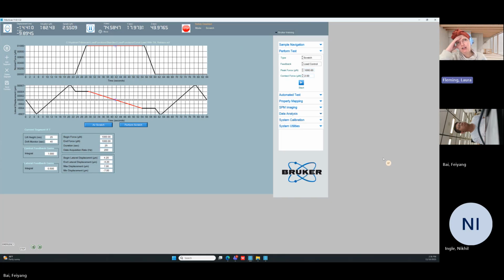I have a customer who has a temperature stage, which you don't have, and they are heating a diamond-like coating and doing indents on it. The probe is also diamond. They get 8 indents per probe before it's no longer usable because they blunt it so much, because heat is so hard on diamond. So there's no warranty once it's in use. Obviously, if it's defective, that's a totally different conversation that we would have.